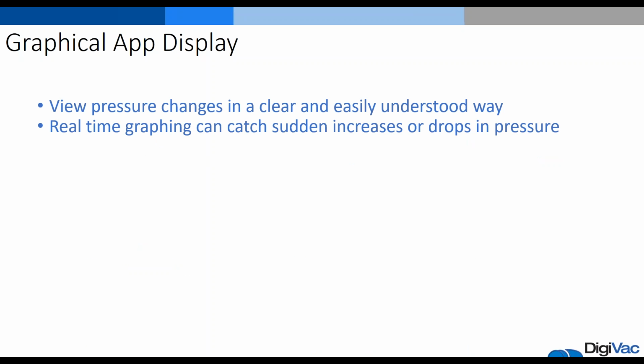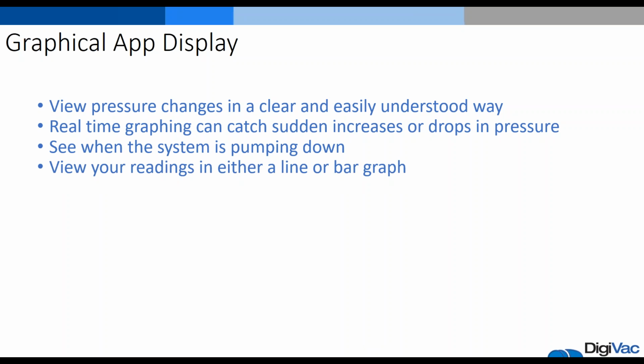The graphical app displays allow you to view the pressure changes in a clear and easy to understand way. And the app itself allows for real-time graphing, which can catch sudden increases or drops within the pressure. So you can have the graph open on your phone, and you can be watching the pressure changes in real time, in a time interval that you set: once every minute, once every hour, once every 5 minutes if you choose, or you can do it within a matter of seconds or 1 day. And then you can see what the vacuum is. You can see when the system is pumping down, or you can view your readings in a line or bar graph.